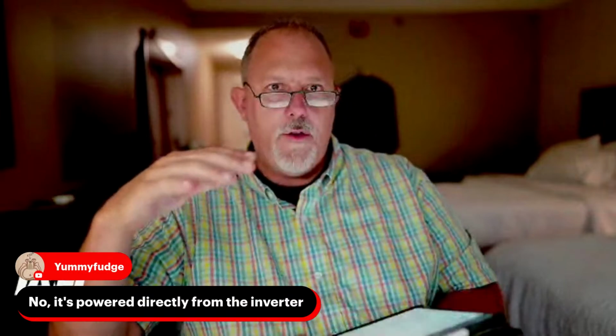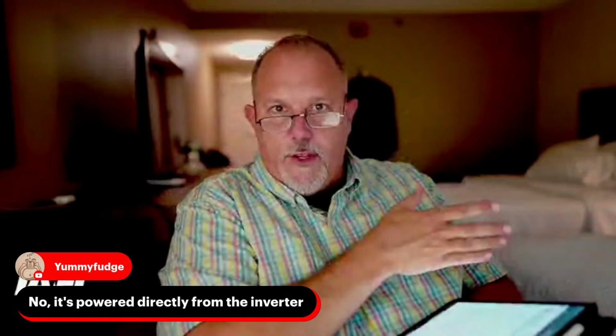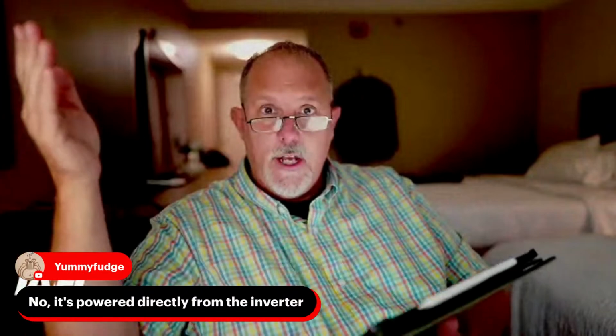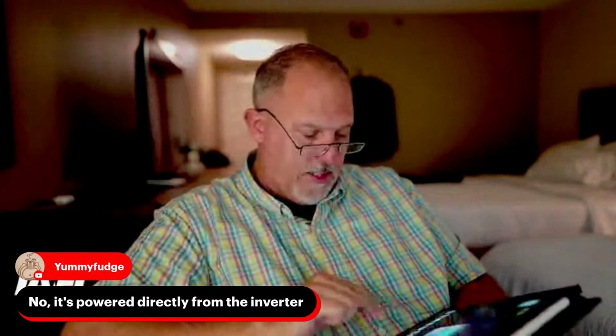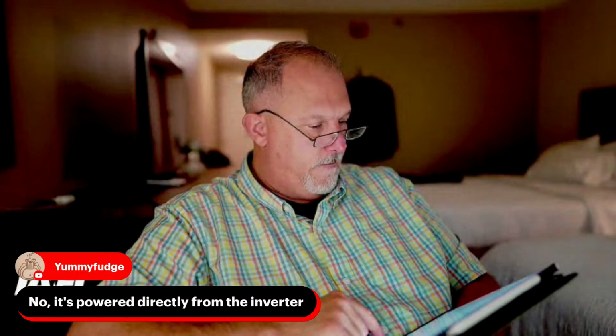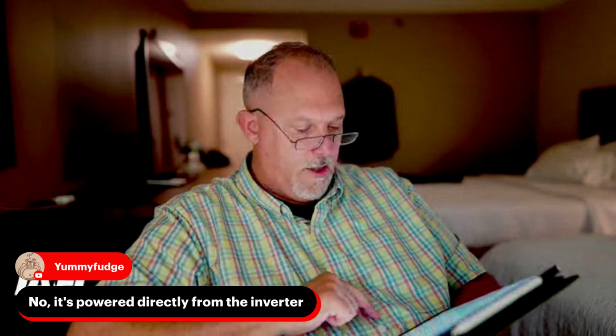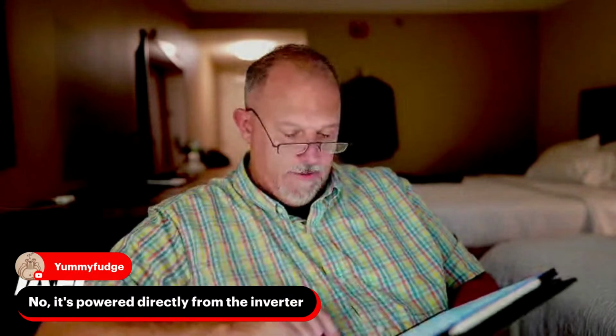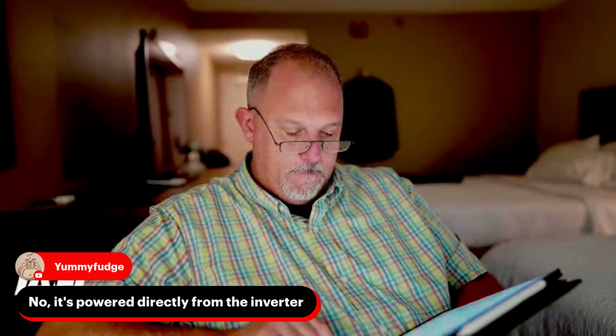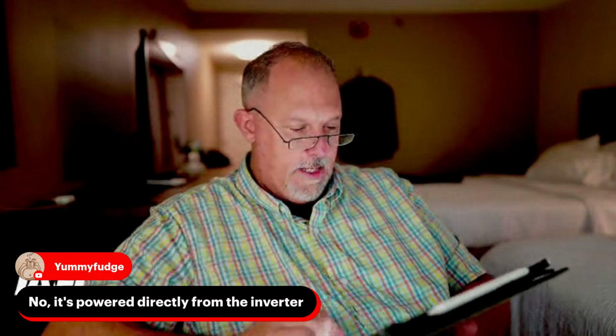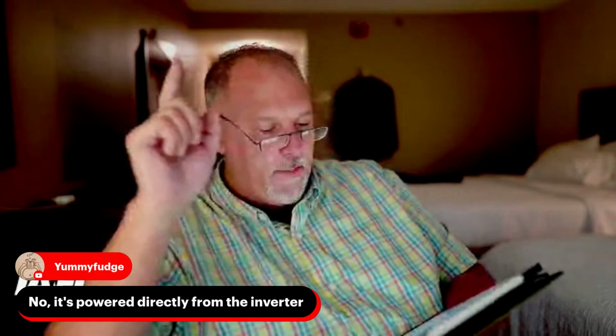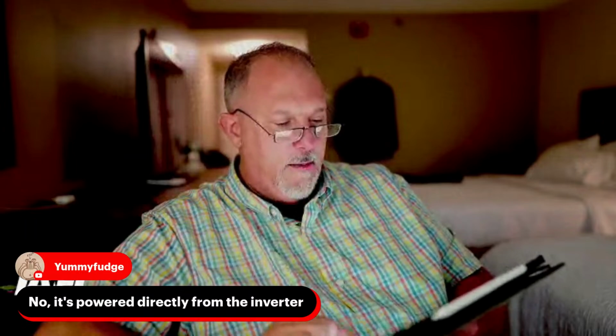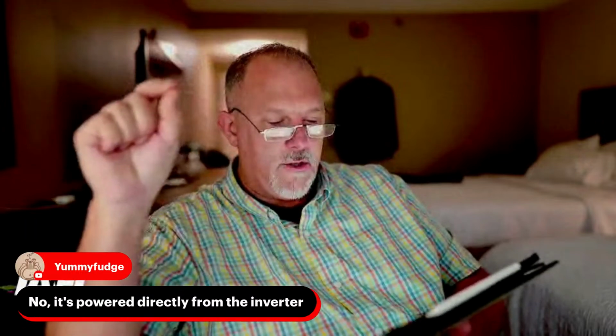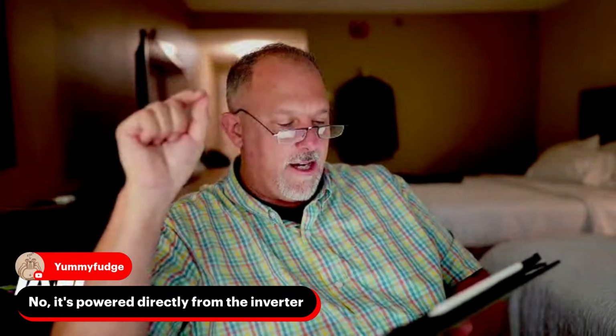Because now you're basically on an island. You don't have a utility service where you do all your bonding and grounding. You don't have a separately derived system, apparently, because you're saying that the inverter is not a separately derived system. And I'm missing Code Panel 2, Task Group 3. In standalone systems, they have to be listed, they have to be evaluated. Power production sources, circuit conductors between standalone sources and structure disconnecting means shall be sized based upon the sum.